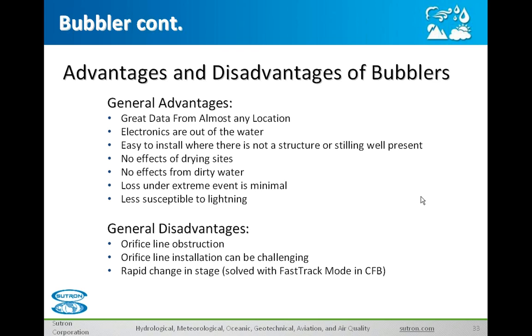Some disadvantages: there are some cases when you can get obstruction on your orifice line. Many sites have seen several feet of sediment over the orifice line, and purging is not going to take care of several feet of sediment. Boulders can also affect your orifice line and data. One problem in the past has been that if stage changes rapidly, sometimes the bubbler struggles to keep up with it — the constant flow bubbler, however, has a feature called fast track mode that Paul will address.